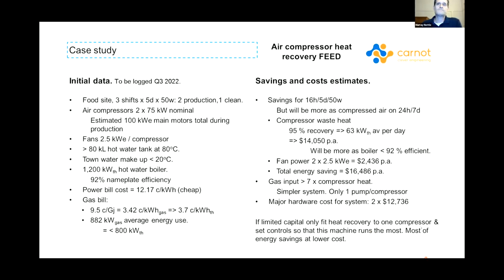Quick case study, it was a boiler. Nameplate was 92% efficient. As we heard earlier, they're usually a lot worse than that, only about 70% efficient. They had a very cheap power bill and a very cheap gas bill. You can see that the effective thermal cost of power, the cost of the energy in heat terms, was about 3.7 cents compared to 12.2 cents for power. But even then, going through the rest of it, we're saving around $16,500 in power for about $25,500 in major hardware costs.